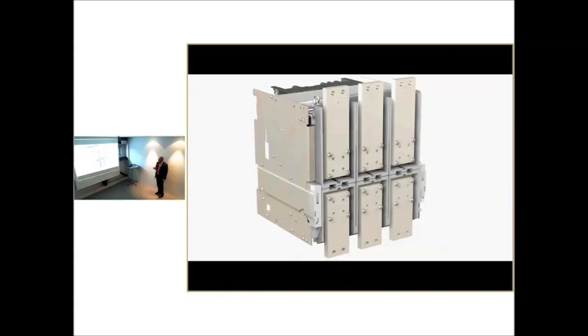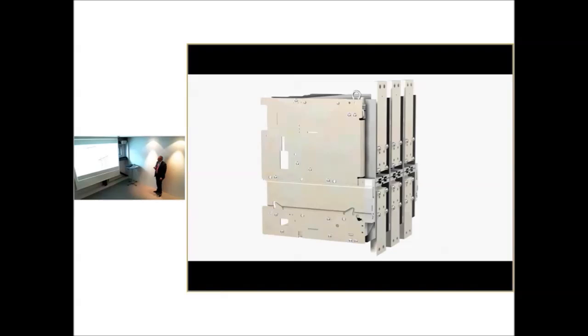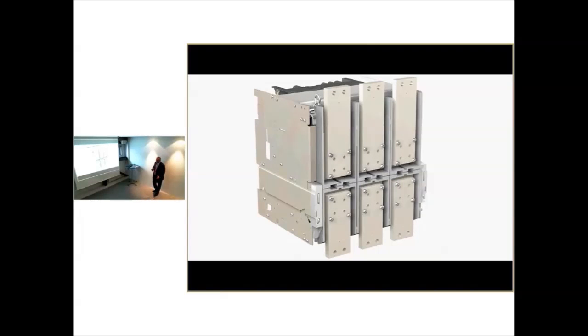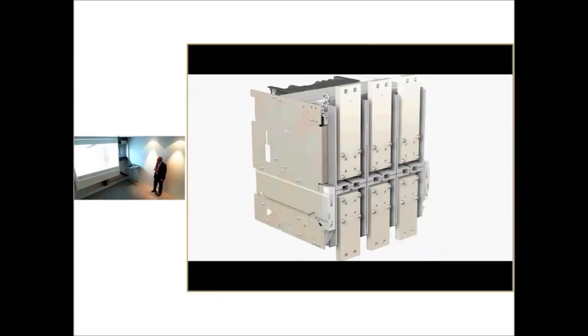These terminals do not increase the depth of the breaker. It's very important that everything is kept. Whatever terminal you use, you have the same depth. You can have a phase separator. You have these slots here that you can have in vertical and in horizontal position the phase separator.